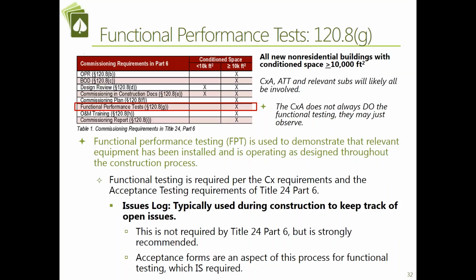Functional performance testing. So now we're going to be talking about that whole acceptance test technician versus functional testing. Functional performance testing, in terms of standard commissioning practices, is only required if that non-residential conditioned space is 10,000 square feet or more. But we also have acceptance testing requirements in California that have to be done all the time. So functional testing may include acceptance testing, but usually functional testing has a different methodology in terms of keeping track of what's happening with acceptance testing or functional testing and the results of that testing. Acceptance test technicians can never ever walk away saying we didn't make sure it was working, which might be happening in functional testing. You're keeping track of the fixes, how many times did we go back and deal with this, what are some issues that might have happened in terms of integrating that design into the actual construction practice.